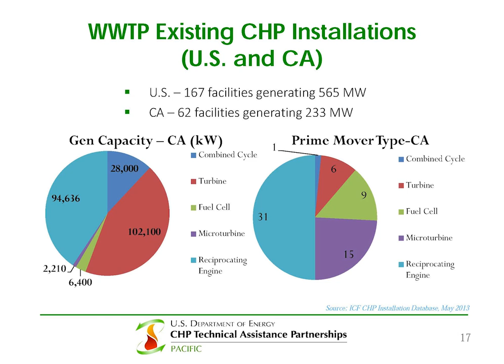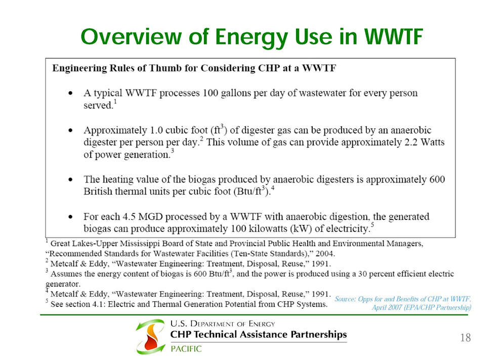A good rule of thumb when considering CHP at a wastewater treatment plant is to utilize anaerobic digestion for biogas. Perhaps most interesting: for each 4.5 MGD processed by the plant with anaerobic digestion, you can generate about 100 kilowatts of electricity.